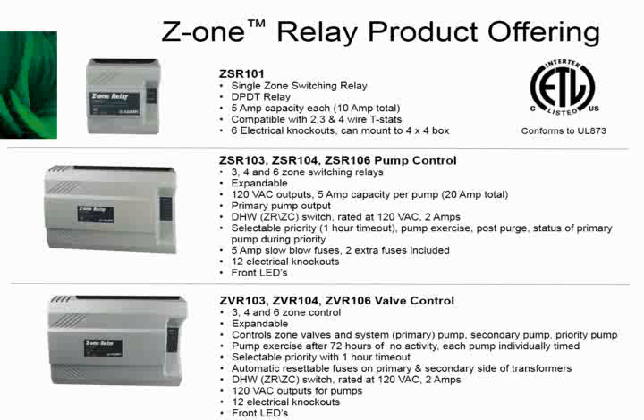We have automatic resettable fuses, and that's actually true on all of the controls. On the 24-volt side, if you would short out a thermostat, it's going to short out that resettable fuse. Once it cools down, it closes back up, and you're up and running again. And we've certainly tested that feature. We know that works. Yeah, we definitely tested that in the lab a few times unintentionally.